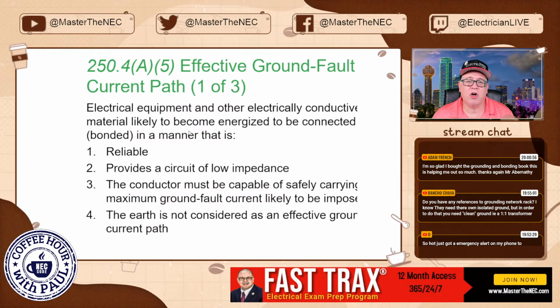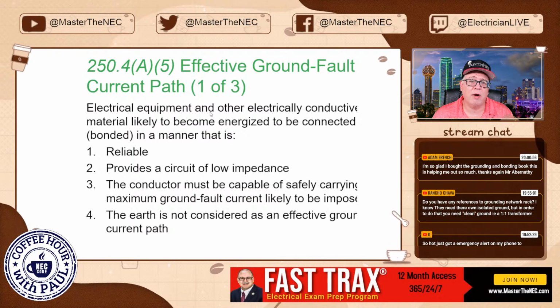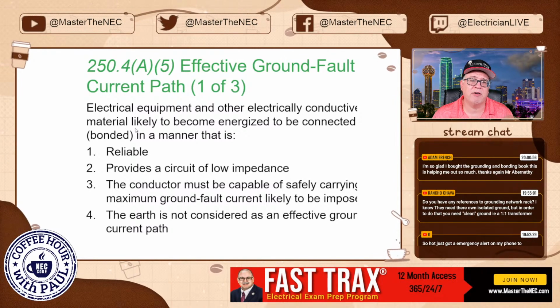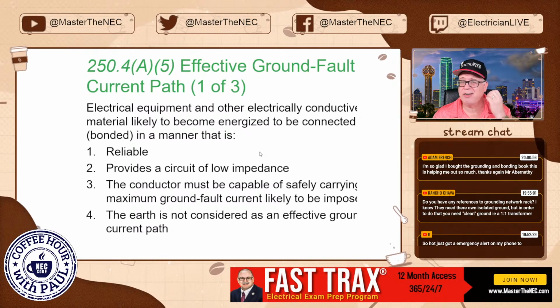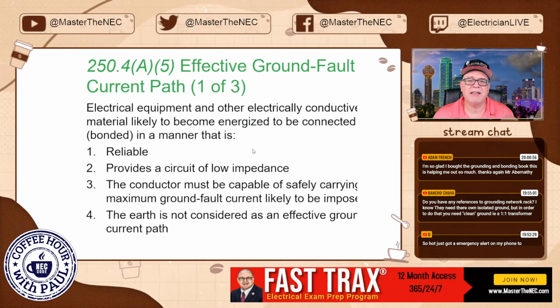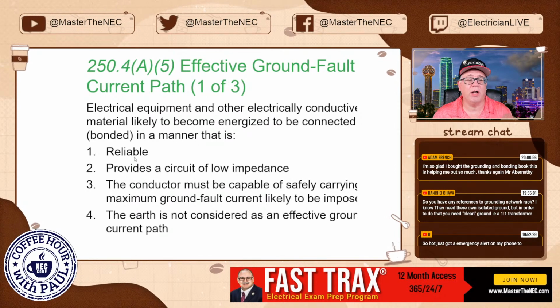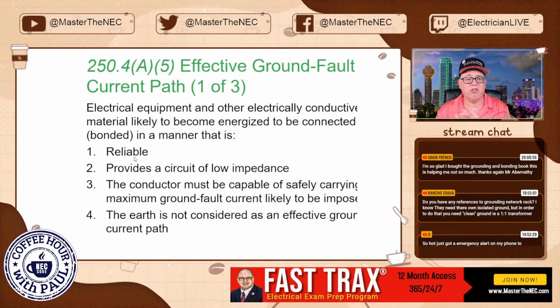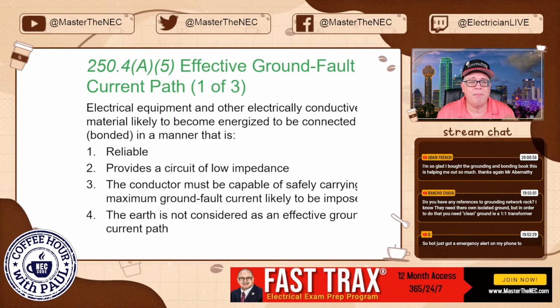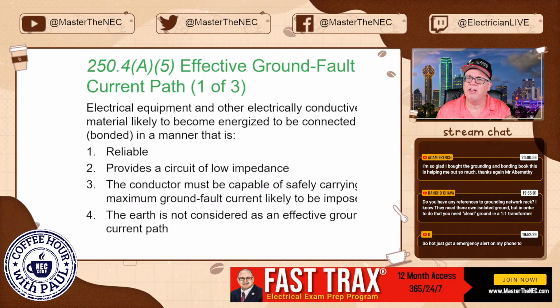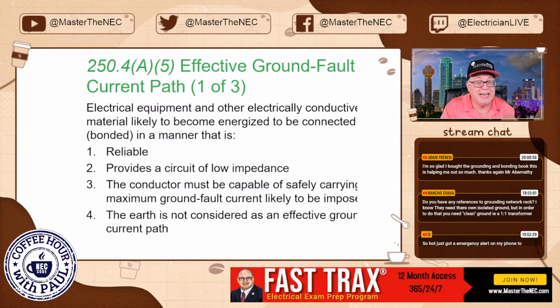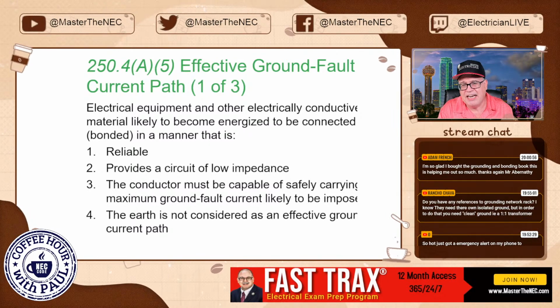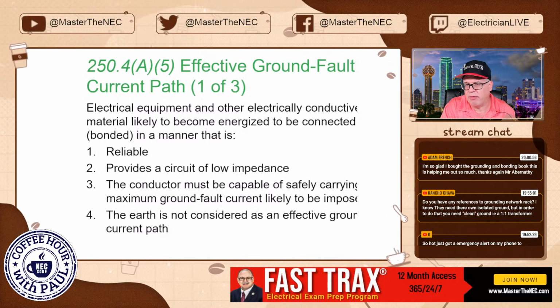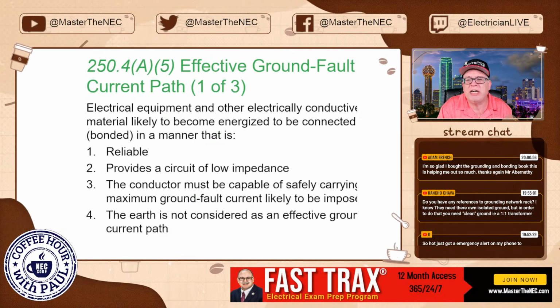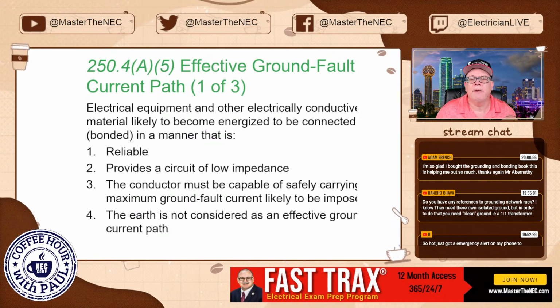250.4A5, effective ground fault current path. Electrical equipment and other electrically conductive materials likely to become energized, there's that term again, to be connected or bonded in a manner that is, number 1, reliable. Number 2, provide a circuit of low impedance, means we have to construct an effective ground fault current path. Not just a ground fault current path, an effective ground fault current path. One that we intentionally create, okay?